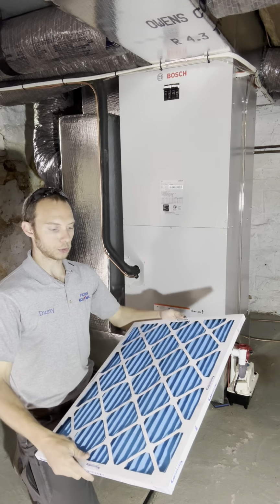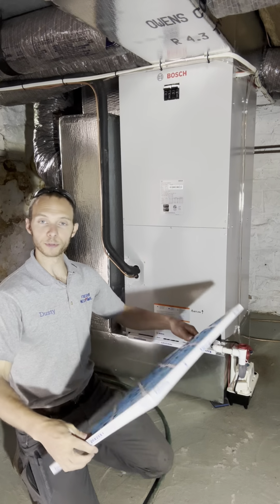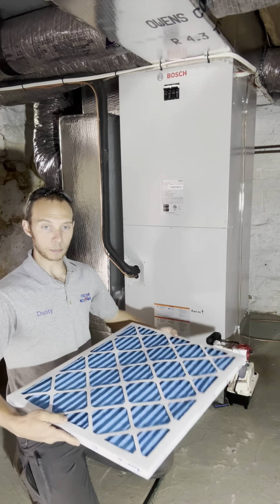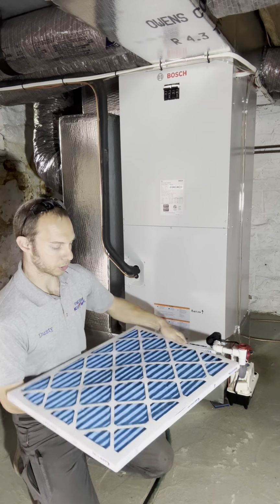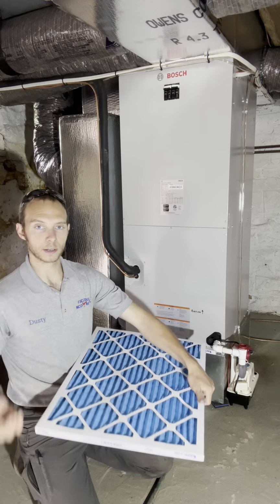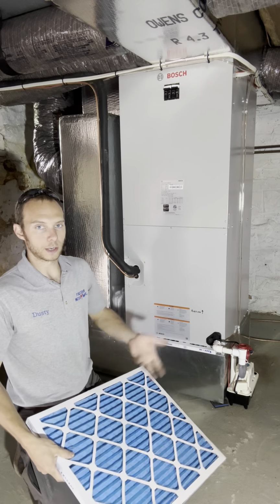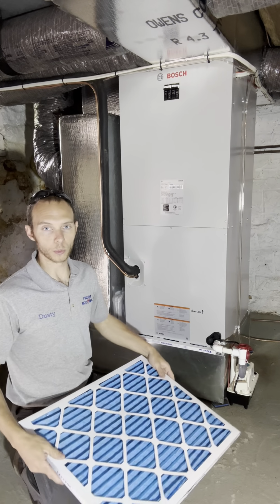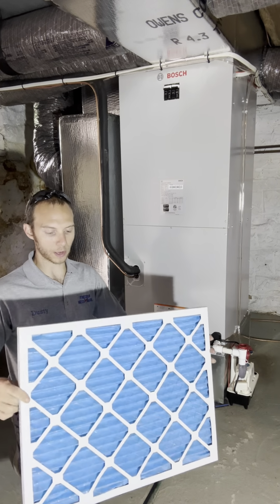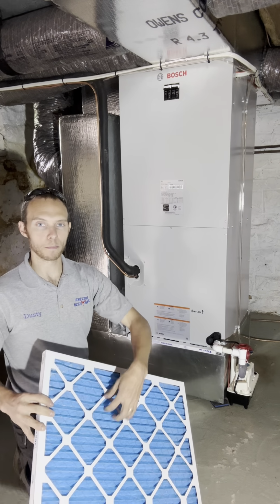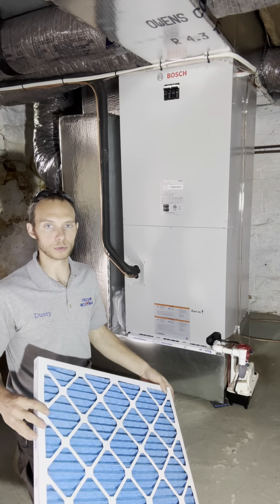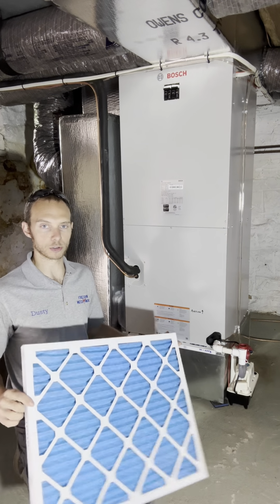So the issue is that some people forget their air filter and it becomes clogged, so it starts to push up in the center, and it can tear through, and then you end up with a clogged coil or other issues that way. So that's why they're directional. They put that metal mesh in there to prevent issues if somebody forgets to change their air filter.